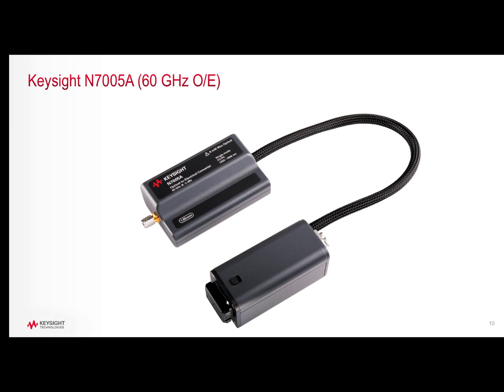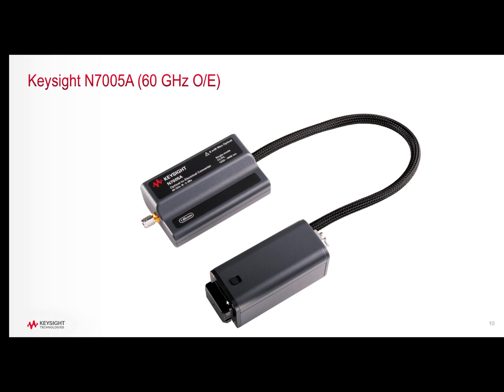This concludes the summary of Keysight's new N7005A optical-to-electrical converter module for use with Infiniium UXR series real-time oscilloscopes. This brings four channels of time-synchronized acquisition to this traditionally equivalent time world of optical measurements. The combination of the N7005A and the UXR series low noise makes this technology introduction a uniquely valuable tool set for 800G optical research requiring optical error detection, advanced equalization, clock recovery, as well as the capabilities of conventional optical measurements such as TDECQ.